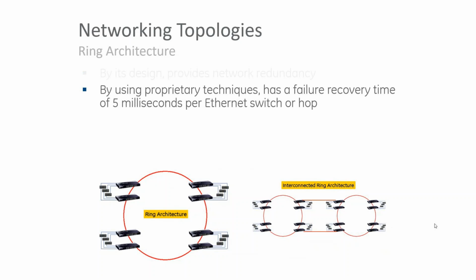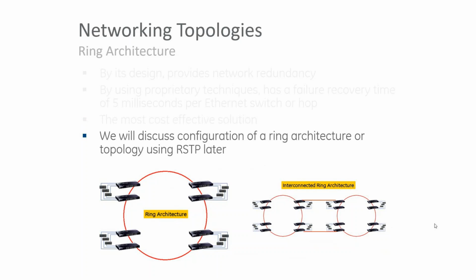Using proprietary techniques, ring recovery time when you lose and then recover a connection can be less than 5 milliseconds - Cisco has some proprietary methods, and a lot of this is proprietary. There is one standard called RSTP for ring architecture. If you have devices from different manufacturers, you want to use a standard like RSTP, because you can't build a ring across manufacturers if one implements a proprietary standard for ring reconfiguration.